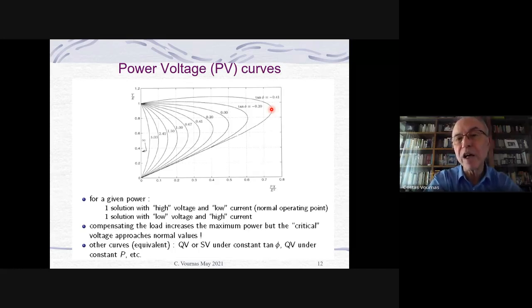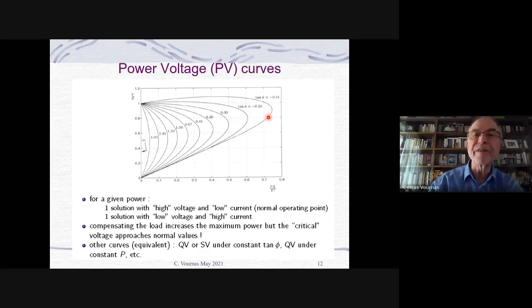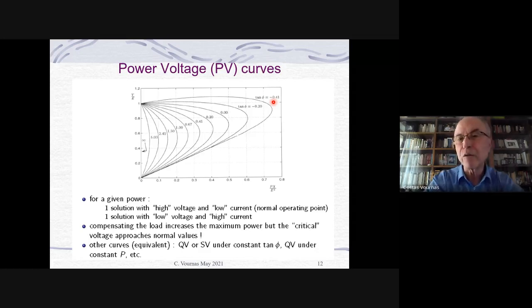This is one reason we need very detailed studies for voltage stability: if we have compensated networks, producing reactive power to increase power transfer, then the voltage where I have maximum power, which is the voltage stability limit, can be very close to nominal voltage. So keeping the voltage close to nominal does not mean you are safe from voltage instability.